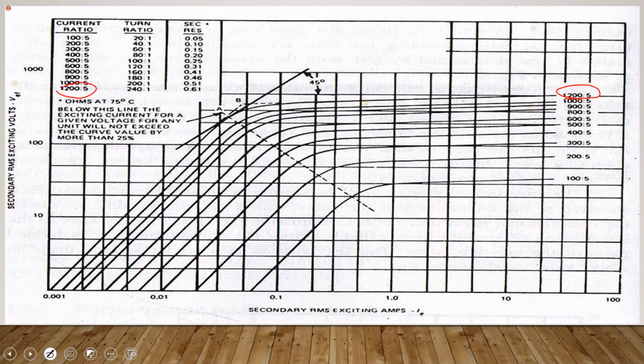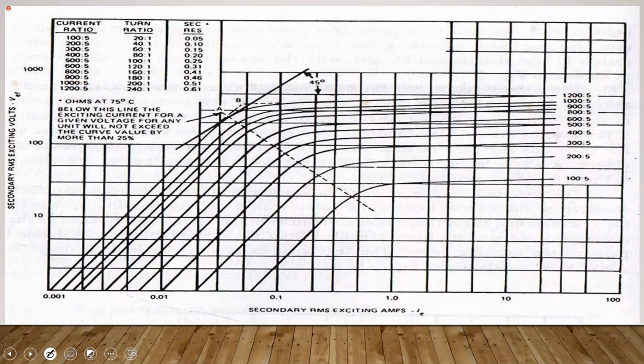All right. Now, I did say it's a multi-winding CT. So it's 1200 to 5. However, what that is also saying to us is that in order to get 1200 to 5, because you're using the maximum number of windings from the CT, it means that it will also give you the largest impedance. Yes?